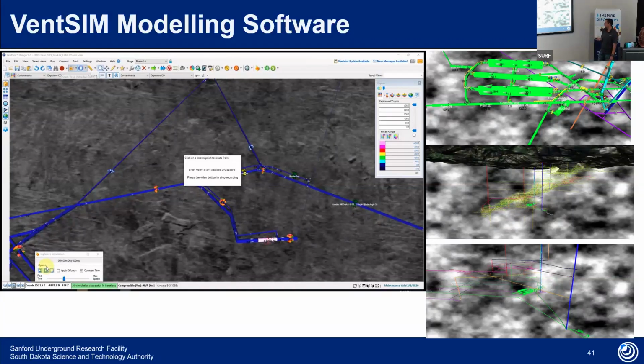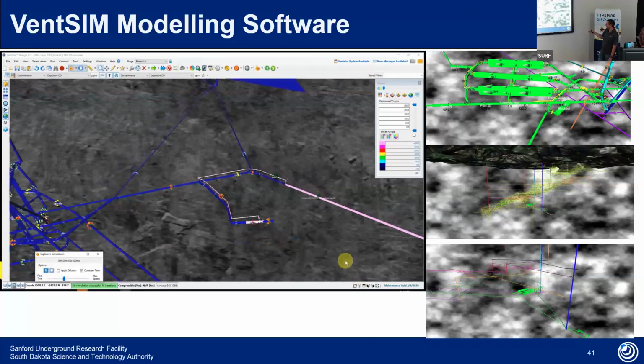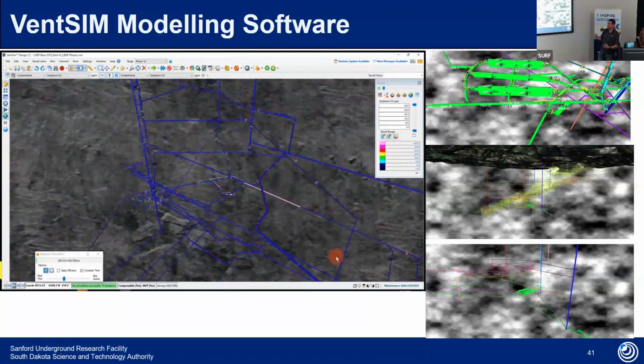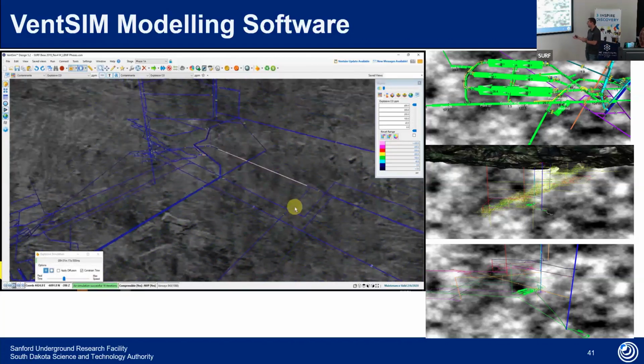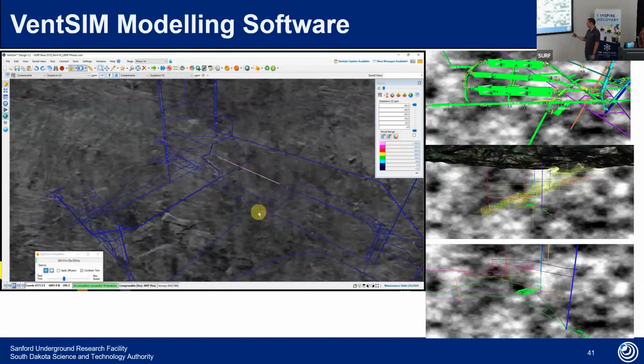This video was actually done with Kiewit during the pilot drift excavation. Everything in blue shows good, clean air. This is during a blast, and everything in light pink shows blast gas. We're showing them how we design our systems — the negative pressure system in this case — where it's going to go and who it's going to affect. In this instance, we actually closed off certain levels above us, restricting access so no one would get into that vent stream and get blasted with blast gas.